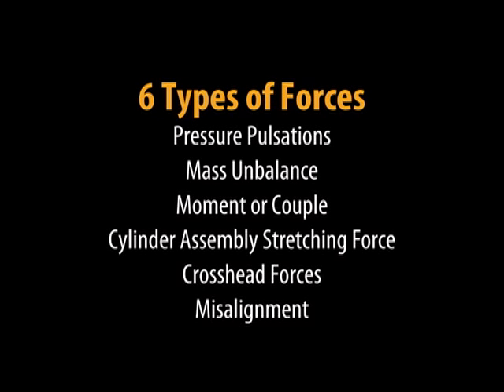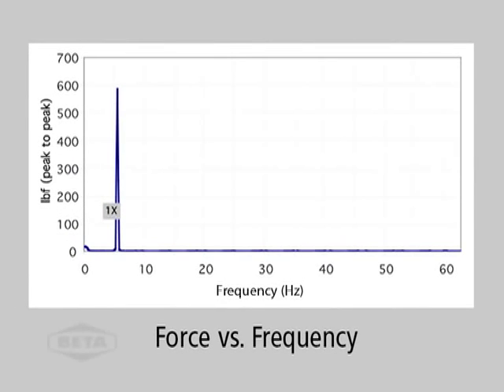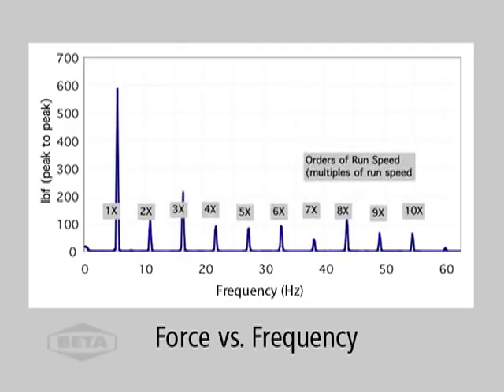Now that we have defined the six types of forces, we can look at their total impact on a compressor package. This chart shows the magnitude of the force at the fundamental frequency or one times run speed. There are also forces at higher multiples of run speed such as two times, three times and so on. These higher order forces are also called harmonics. Pulsation forces and cylinder stretching forces are examples of forces that occur throughout every multiple of run speed. So you can see that forces on the compressor occur across a wide range of frequencies.